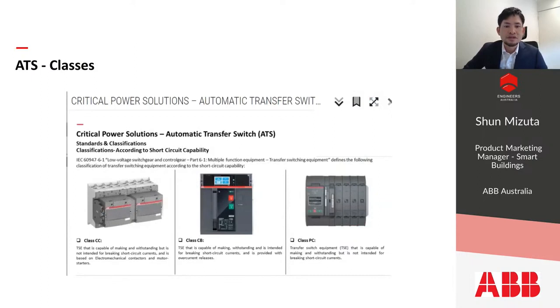Now let's look into the different classes. Class PC and Class CC, which are contactor base or switch base, are more cost-effective solutions, but they don't have circuit protection functionalities. Whereas Class CB has overcurrent and short circuit protection. It is more expensive, but it can usually cover higher current ratings as well.